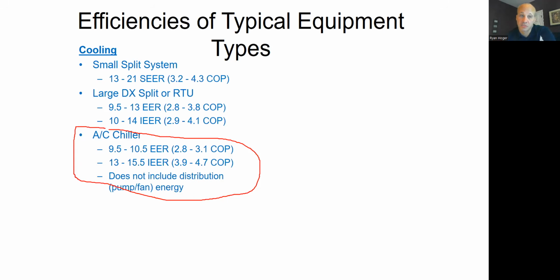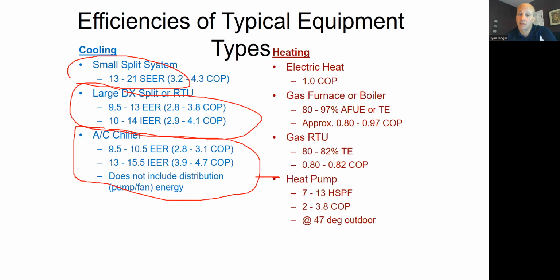Small split systems include their fans. Rooftops include their fans. VRF includes their fans and any circulation, which in this case is the compressor energy to push refrigerant long distances. So if you want to compare these things, it becomes really challenging. They all use different systems of efficiency ratings, different testing, and some of them do and do not include some of those components. So you cannot directly compare them. The same thing happens on the heating side of the equation with those same pieces of equipment.